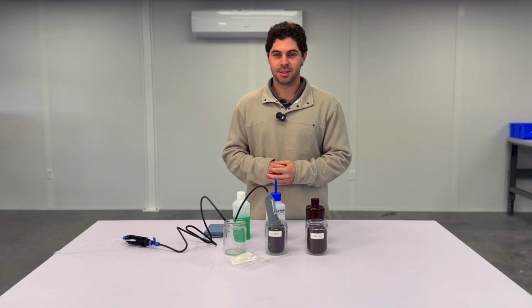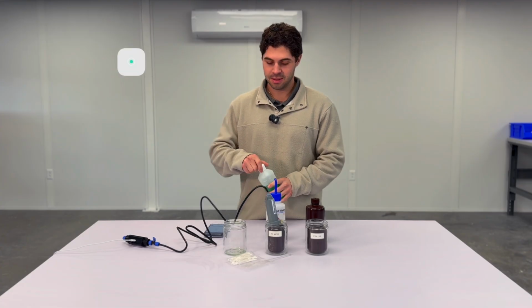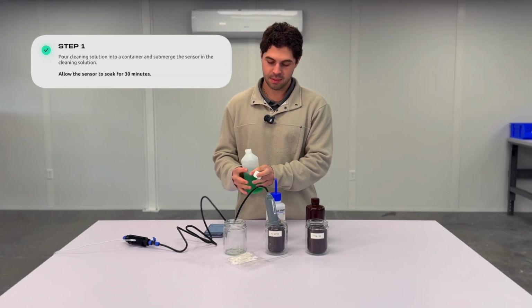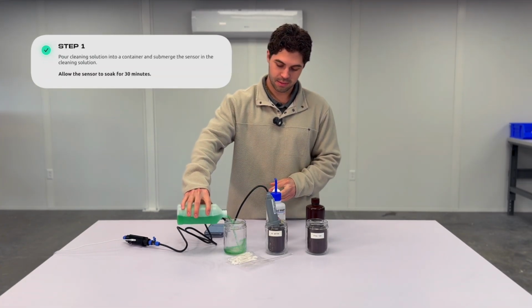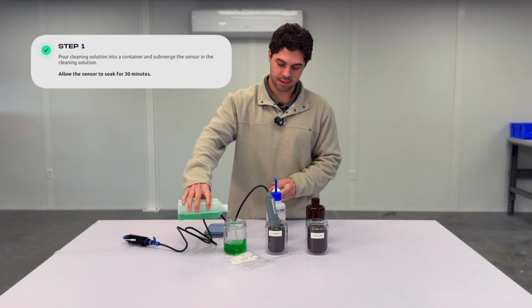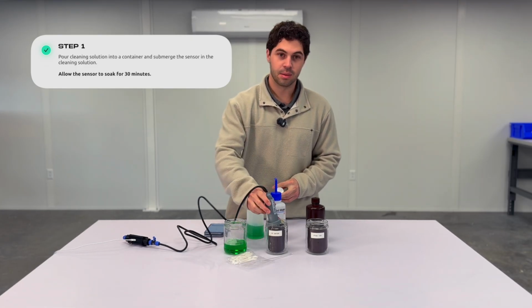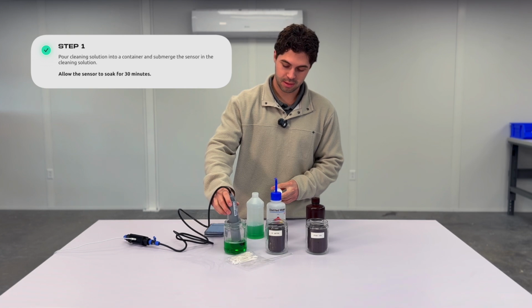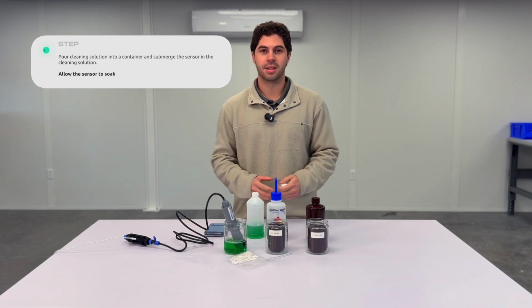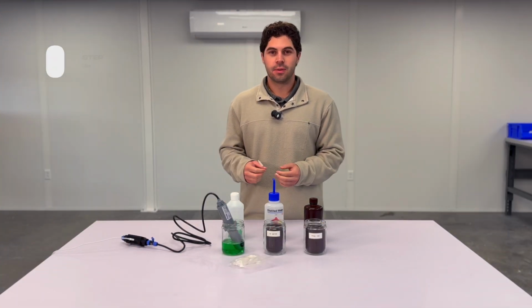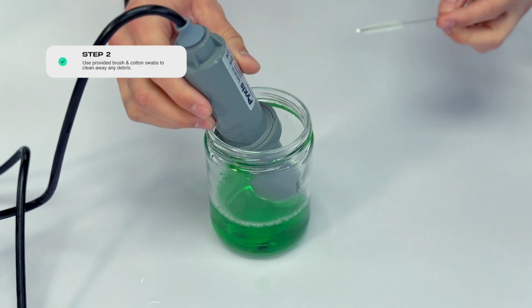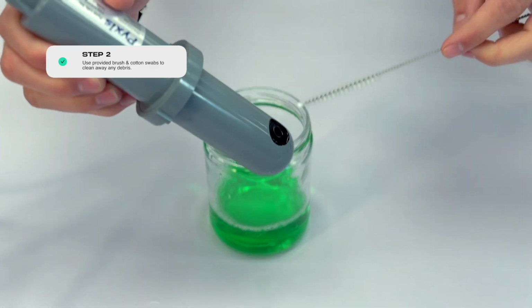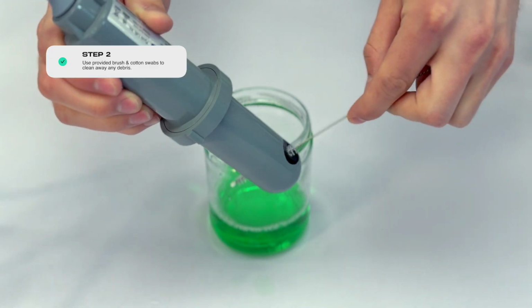Now to clean the sensor, you're going to take our probe cleaning solution, pour it into a container. You're going to want to pour enough that the sensor eye is fully submerged, and then place the probe in the solution and let it soak for about 30 minutes. After you've let it soak for 30 minutes, you want to take it out. Start with a nylon brush, clean any gunk out that might be in there.